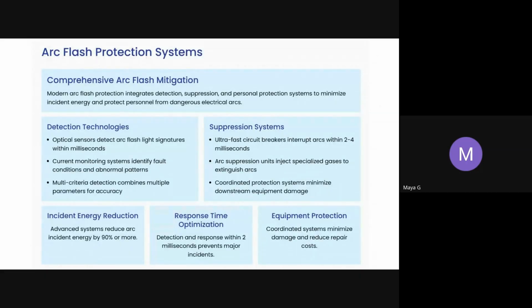Once the detection is complete, we have to suppress the anomalies. For that, ultra-fast circuit breakers that interrupt the arc within 2 to 4 milliseconds are available. The arc suppression units inject specialized gases to extinguish the arc. Coordinated protection systems minimize downstream equipment damage. We had already discussed ZSI in a similar fashion. The damage on the protection systems is reduced by using ZSI.